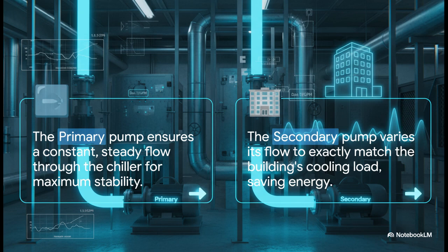Now, to be really smart and efficient about this, engineers often use a clever trick. They split the job between two sets of pumps. You've got the primary pump, which is all about stability. It keeps a nice, constant flow of water moving through the chiller, because that's how chillers like to operate. But then you have the secondary pump. This is the smart one. It actually changes its speed, varying its flow to perfectly match whatever the building's cooling demand is at that exact moment. This simple split saves a ton of energy.